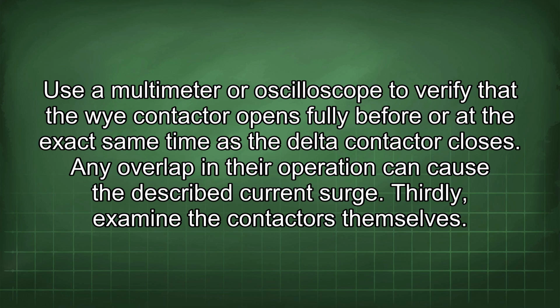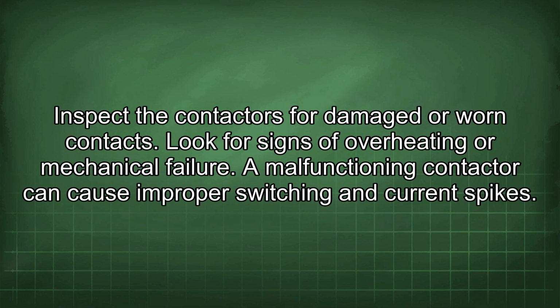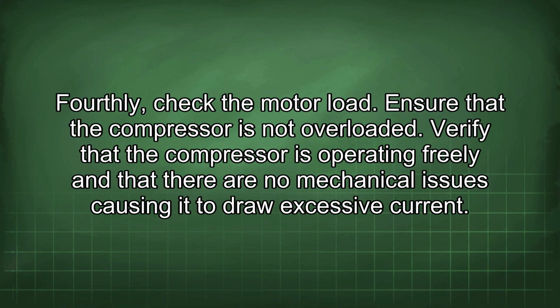Thirdly, examine the contactors themselves. Inspect the contactors for damaged or worn contacts. Look for signs of overheating or mechanical failure. A malfunctioning contactor can cause improper switching and current spikes. Fourthly, check the motor load. Ensure that the compressor is not overloaded. Verify that the compressor is operating freely and that there are no mechanical issues causing it to draw excessive current.